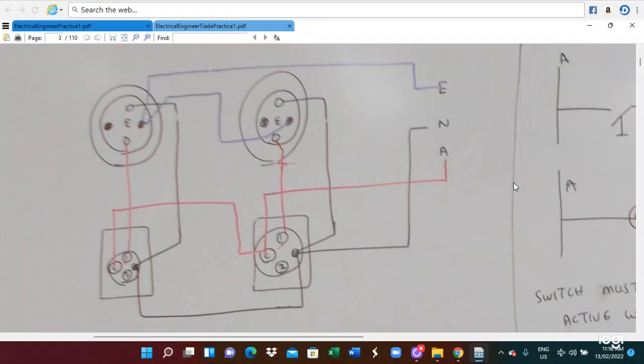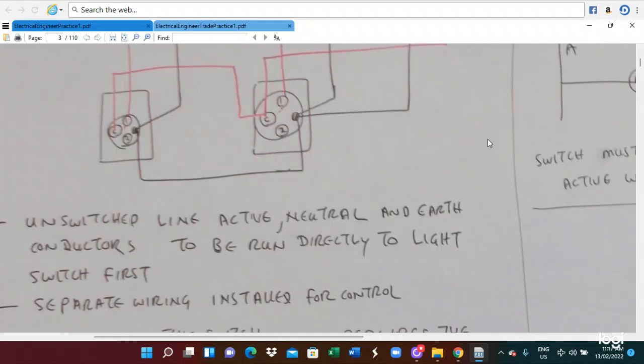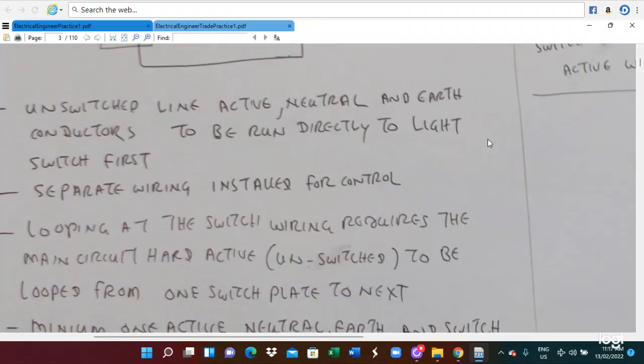Loop-at-the-switch point means the active wire goes to the C point, and from another C point goes to another active wire. So this is the C1, C2 of the switch. The active wire goes to this C point, another C point. And then number 1 is connected to the light wire. Before this point and these two points, we have to connect your light. Out of the opposite side, we connected to the neutral wire. And then an earth terminal is given, so all the earth terminals are joined like this. So this is for the loop-at-the-switch installation.